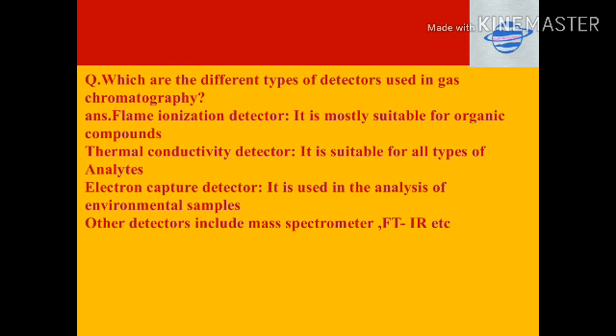Thermal conductivity detector: suitable for all types of analytes. The detector contains two resistors in identical heated chambers — one surrounded by the column effluent gas, the other by identical gas with identical flow but not passed through the column. When the column effluent contains other molecules, it conducts heat slightly differently, giving the resistor a slightly different temperature, which produces a signal indicating a foreign substance is eluting.